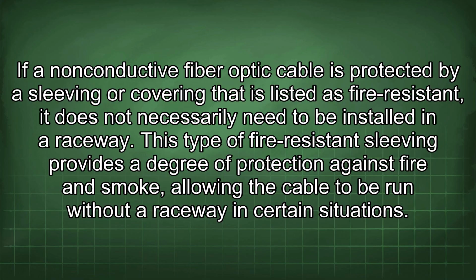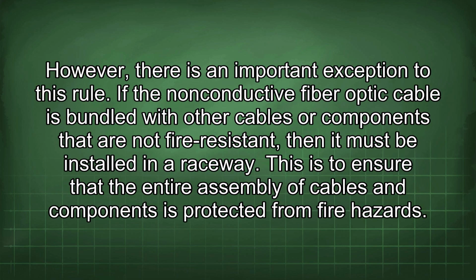This type of fire resistant sleeving provides a degree of protection against fire and smoke, allowing the cable to be run without a raceway in certain situations. However, there is an important exception to this rule. If the non-conductive fiber optic cable is bundled with other cables or components that are not fire resistant, then it must be installed in a raceway.